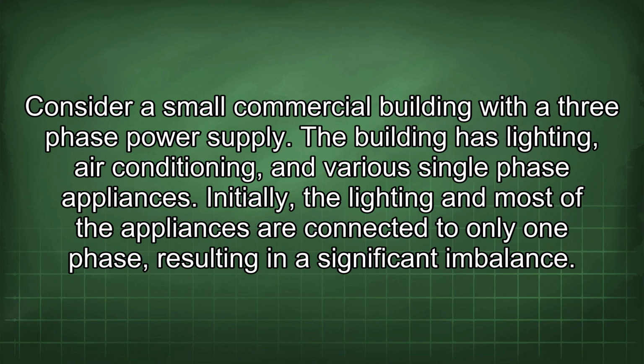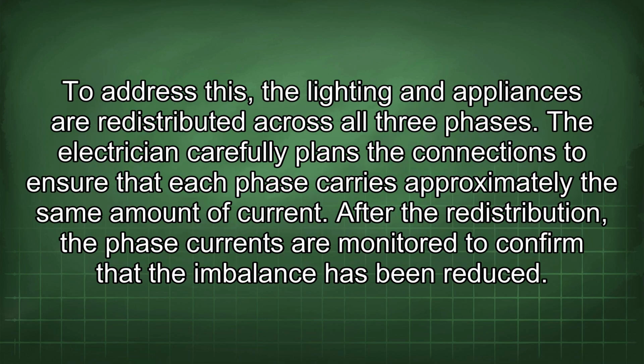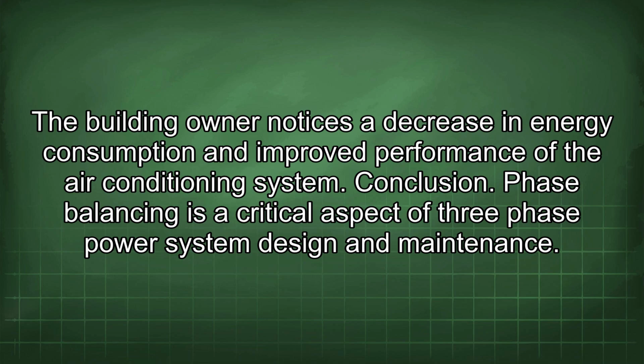Initially, the lighting and most of the appliances are connected to only one phase, resulting in a significant imbalance. To address this, the lighting and appliances are redistributed across all three phases. The electrician carefully plans the connections to ensure that each phase carries approximately the same amount of current. After the redistribution, the phase currents are monitored to confirm that the imbalance has been reduced. The building owner notices a decrease in energy consumption and improved performance of the air conditioning system.